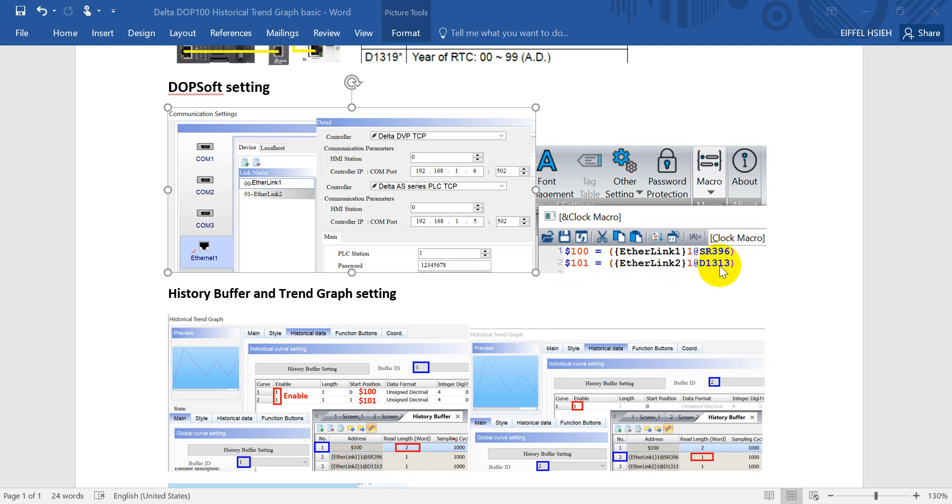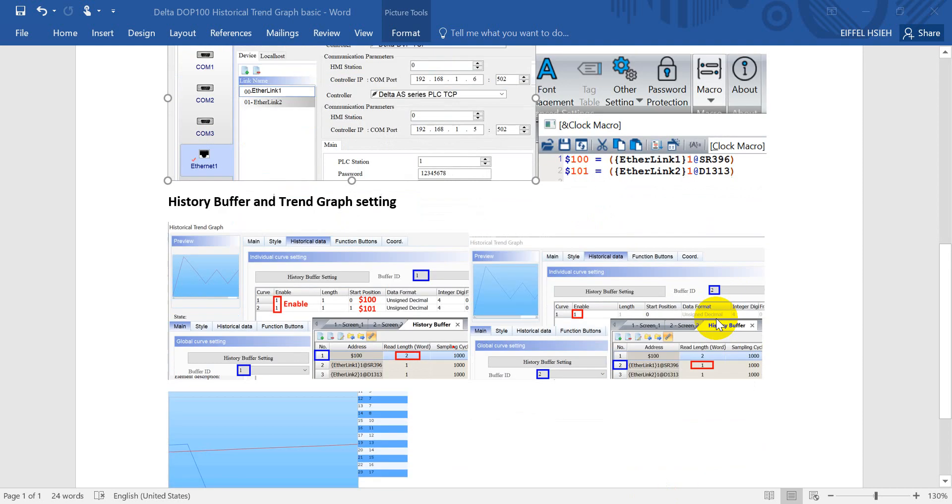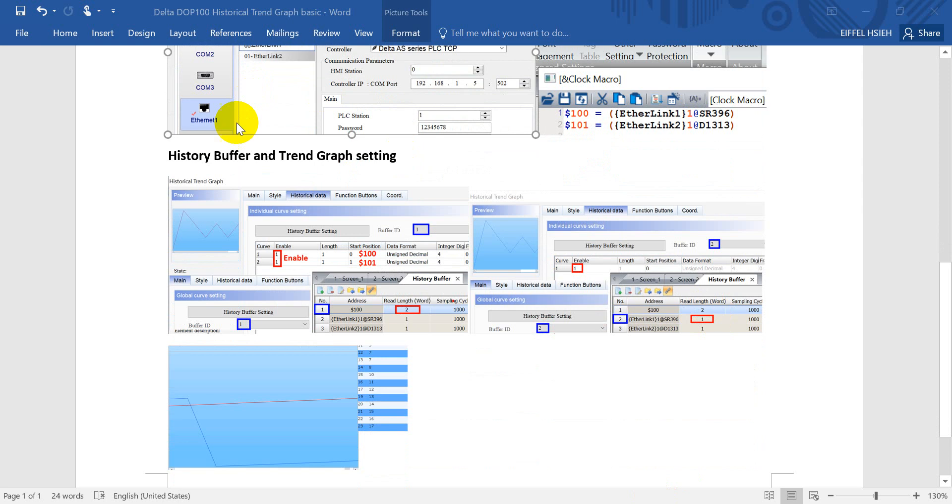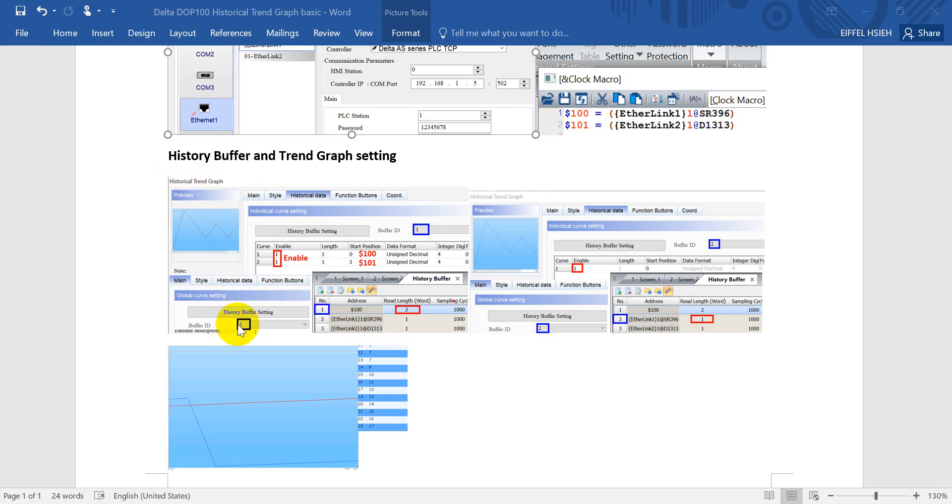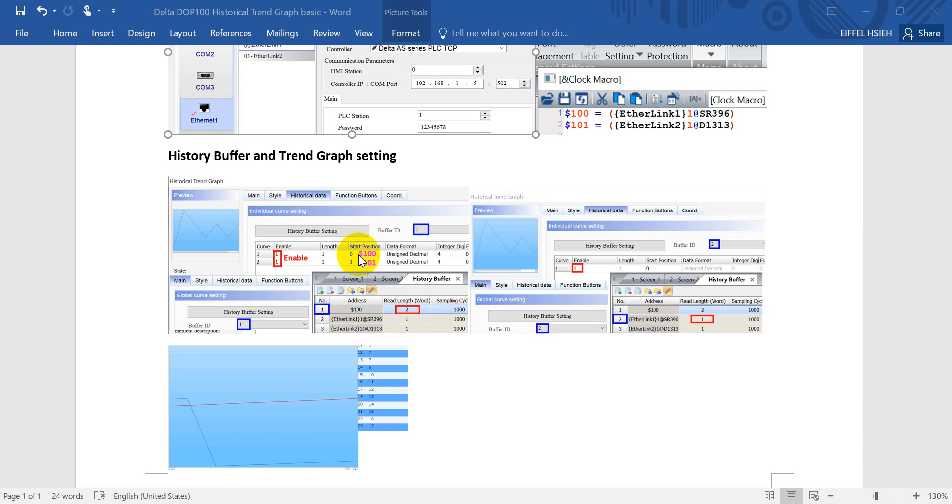Next we'll move to the historic buffer and the trend graph setting. As you can see here we will find a historical trend graph. First you can select a buffer ID and this buffer ID will actually relate with the history buffer where you set. One means the number one and then you can set how many words you want to read. In this example we just read the two words so that means dollar sign 100 and 101, so that means we also need to enable these two then we can see these two curves.